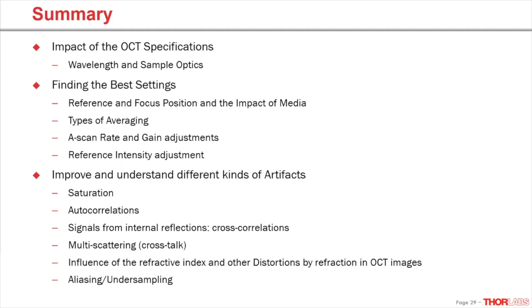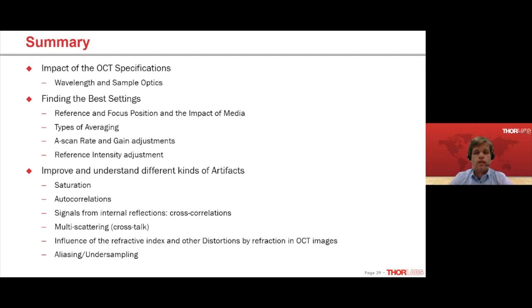Thank you very much, Sebastian and Steve, for these really interesting insights. First question from Sarah: does changing the imaging medium — for example submerging the sample in water — change the depth resolution of the OCT image? The short answer is no. In water you do get a better resolution, but your sample has its own refractive index. If you're imaging tissue in air or submerged in water, the tissue still has a refractive index of about 1.4. In both cases you get the same resolution for the tissue sample, which is the OCT system's resolution divided by 1.4.